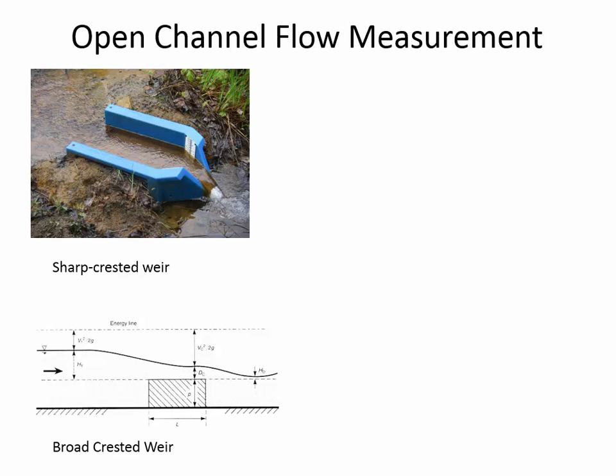Open channel flow is also really common in wastewater treatment, especially when flow starts coming into the treatment plant. One way of measuring open channel flow is with the sharp-crested weir. This picture at first looks like a flume, but it's actually a sharp-crested weir. The way you measure flow rate is through a known relationship between the depth of water upstream of this V-notch weir and the flow rate going through it, which needs to be calibrated before use.